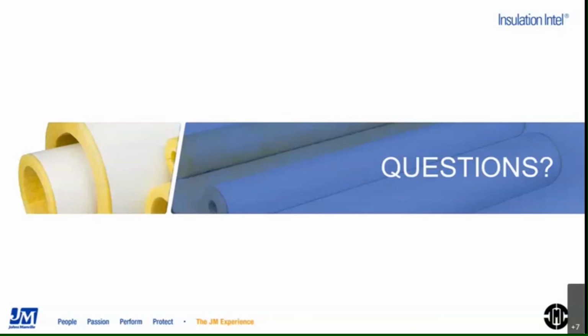You know, a water heater, is it an electric water heater? What's your combustion source? If it's a gas water heater, no, you need to move it. You can't have that in a return plenum, gas or flames. Boiler rooms are generally not a 2550, so to maintain that, you couldn't return that anyhow. So I don't know why the inspector would want a 2550. You can't return that mechanical room. So something needs to be moved. All right. Good to know.